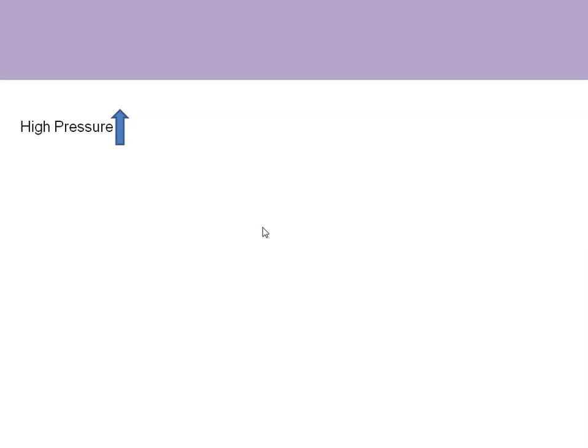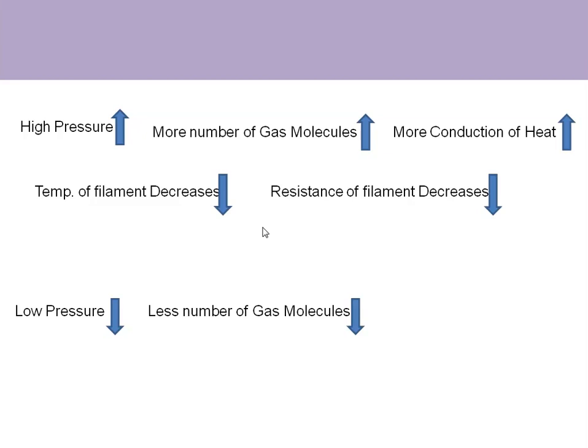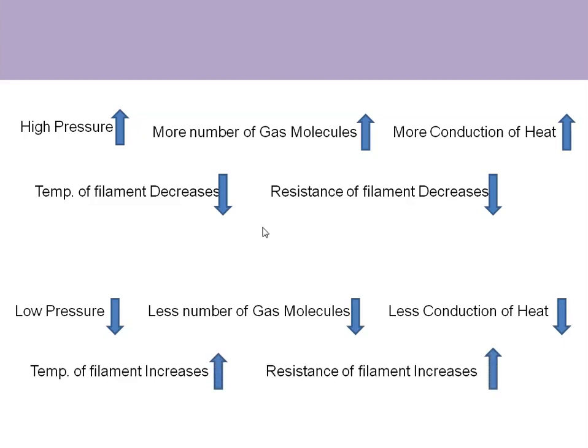When there is high pressure, more gas molecules are present, causing more conduction of heat by those molecules, so the temperature of the filament decreases and its resistance also decreases — because tungsten has a positive temperature coefficient of resistance. Conversely, at low pressure, fewer gas molecules are present, less heat is conducted, so the filament temperature increases and resistance increases. This increase or decrease in resistance unbalances the bridge, and the unbalance is measured as the voltage output of the Wheatstone bridge.